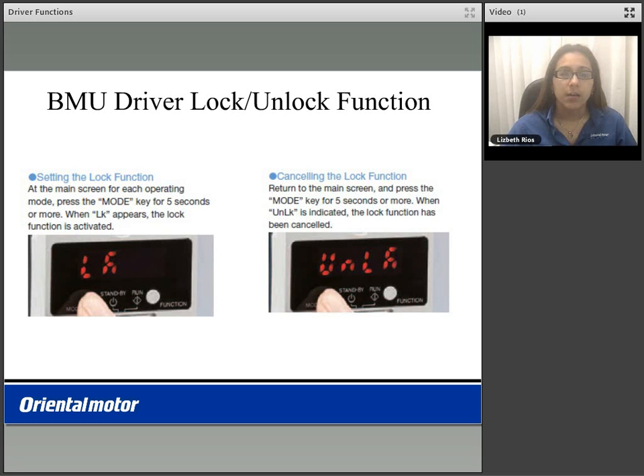The BMU driver features a lock and unlock function when removing the front panel. Once your speed is set using the dial, simply press the mode key for five seconds or more and the abbreviation LK will display for lock. To unlock your speed setting, simply press and hold the mode key again for five seconds or more and the abbreviation UnLk will display, letting you know the lock feature has been canceled, enabling you to vary speed using the dial again.